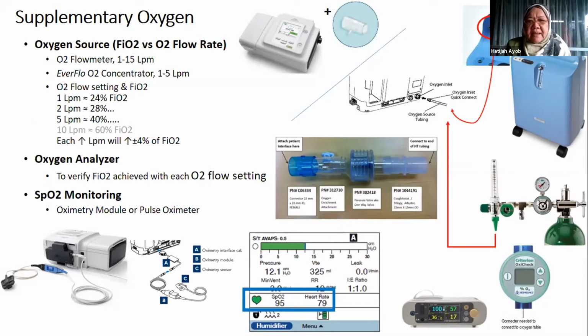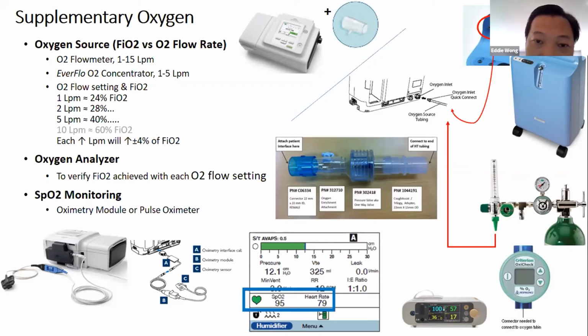Puan Hadijah asks: the room where the patient is, does it have to be air-conditioned? It's good to have aircon for patient comfort, and also because all the medical devices have an operating temperature. Normally, the ventilator is up to 40 degrees Celsius, running 24 hours, 7 days a week. You do not necessarily need to turn on the aircon 24 hours. For patient comfort, let's say they want to go to bed and sleep, that time you can turn on the aircon. Without the aircon, at least turn on the fan so that you keep the room temperature below 40 degrees Celsius, which is good enough already. Most of the devices I show here have an operating temperature that can go up to 40 degrees Celsius.